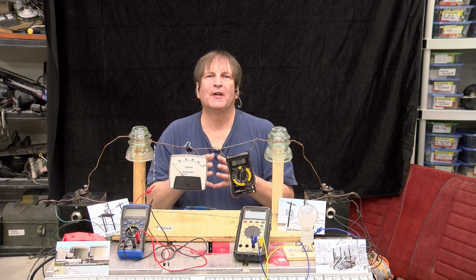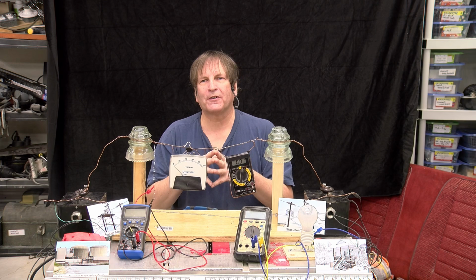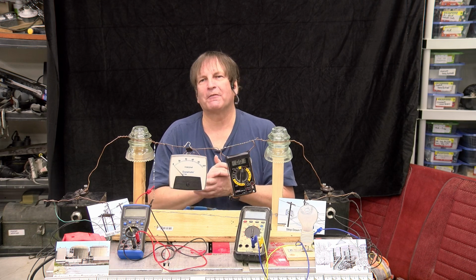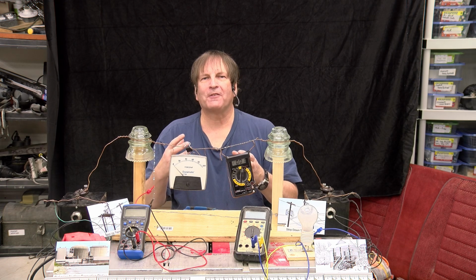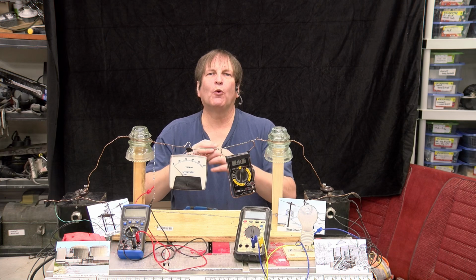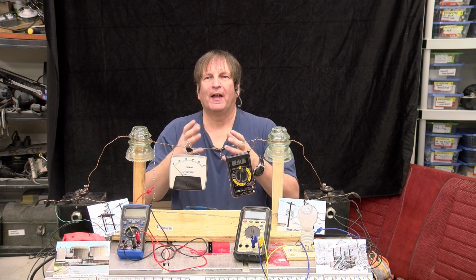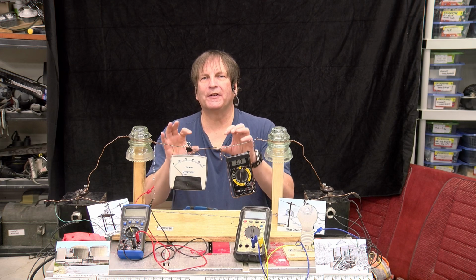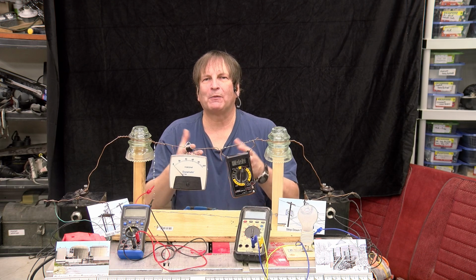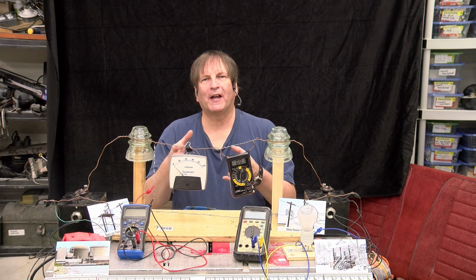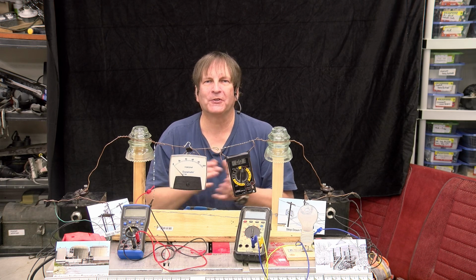So that also means that if you start making a conductor very thick to conduct much more current, well, the truth is the inside part of that conductor does not get used. And one of the ways to reduce that effect is to make the conductor look more like a pipe or something with a larger outer diameter. And so by having the 4 wires near each other like that, we can reduce the skin effect and probably get a lower resistance pathway by having 4 individual wires than one thicker wire where not much current flows through the center.